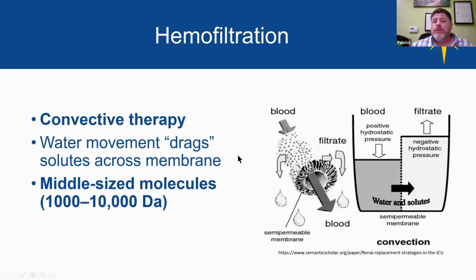When we talk about ultrafiltration, and I know all those names are confusing, hemofiltration, hemoperfusion, I sometimes have to think about it too, ultrafiltration will remove the fluid. In hemofiltration, we actually use the movement of water through the membrane. Here it's illustrated: you have the positive pressure on the blood, the negative pressure on the filtrate, and the water is moving. Because of this movement of water, we're able to pull some medium-sized molecules through the membrane, things that we are not able to do just by diffusion, those middle-sized molecules of 1,000 to 10,000 Dalton. That's the big benefit of therapies that pull fluid through the membrane: first of all, we are removing fluid, but we are also able to get some molecules that have a higher molecular weight.